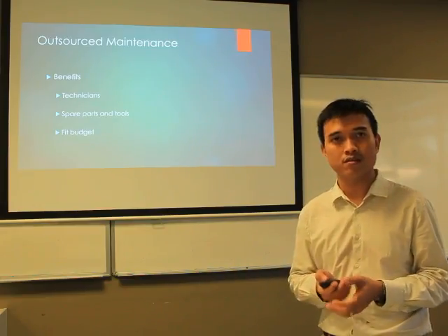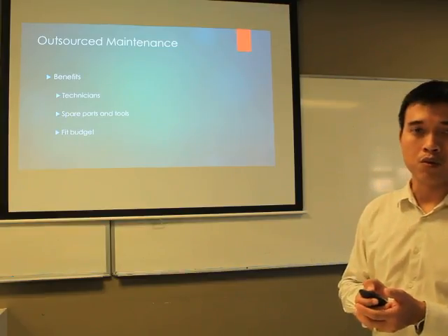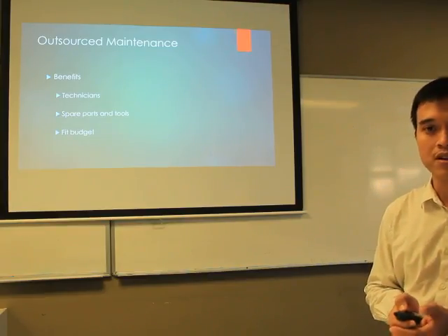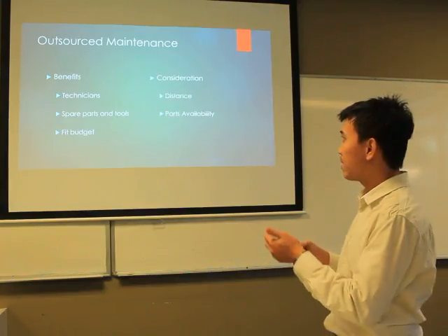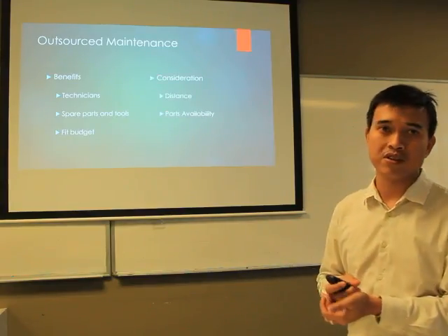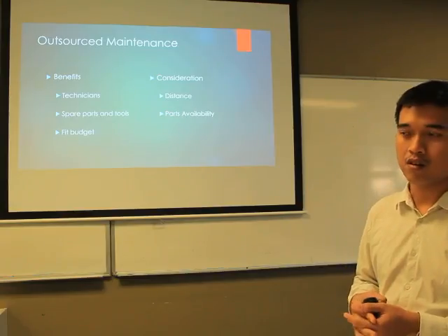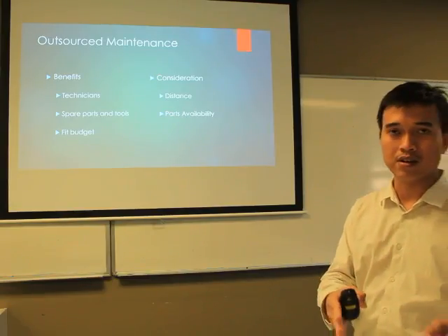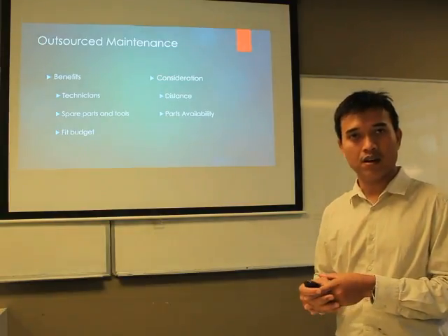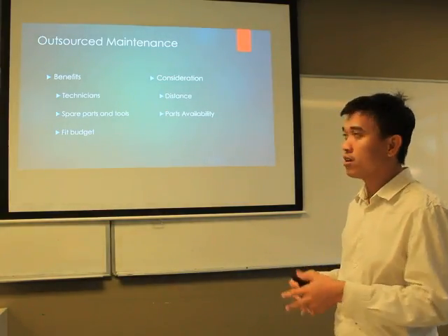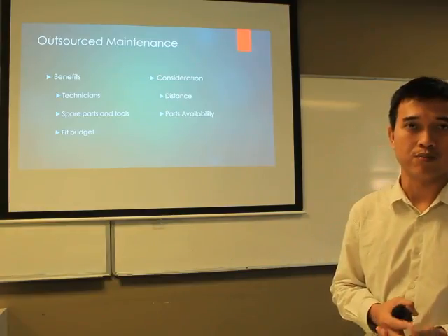However, there are some considerations to think about before deciding to do the outsourced maintenance, and one is the geographical distance between the service providers and the hospitals. The other one is the availability of the spare parts too.